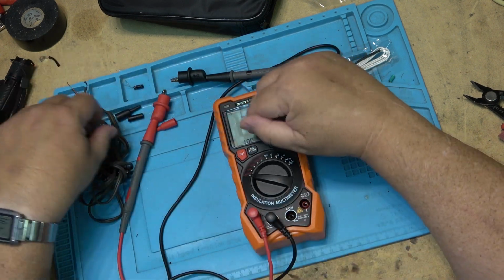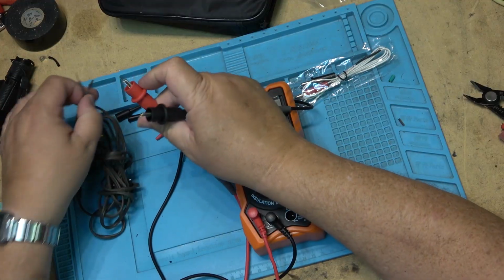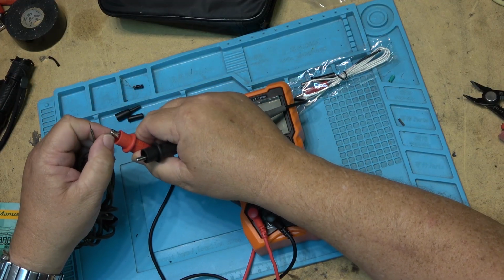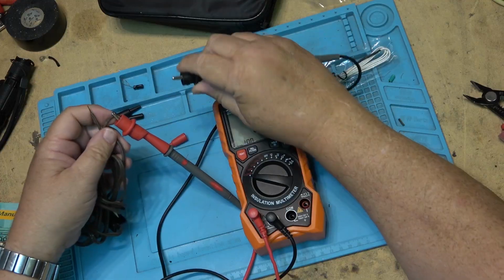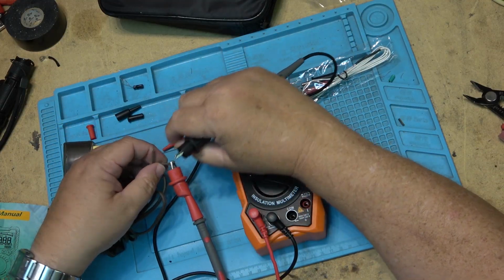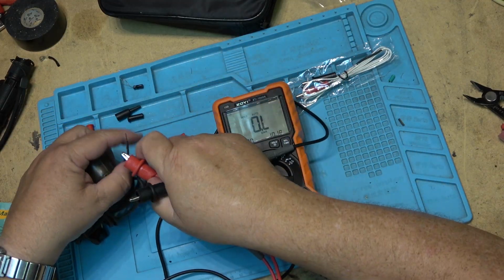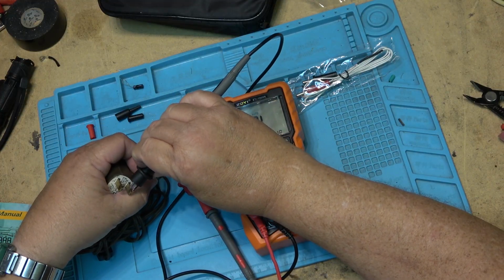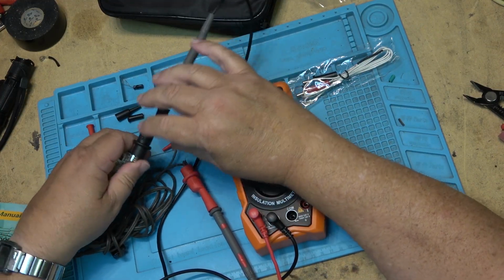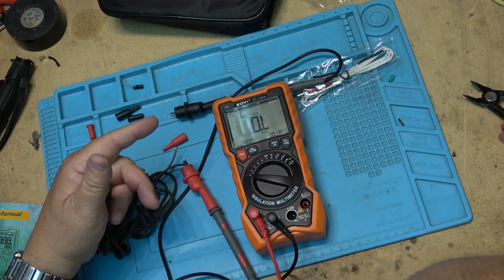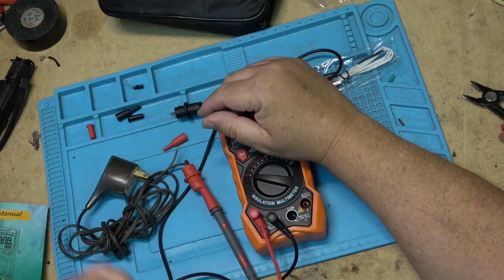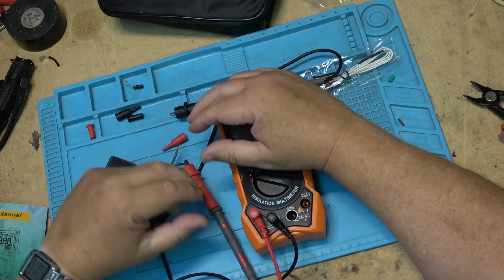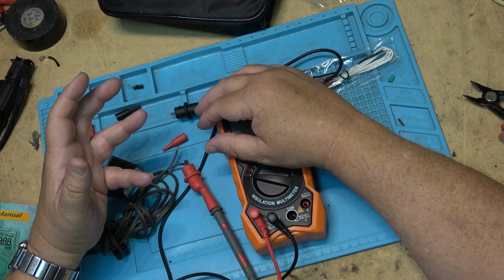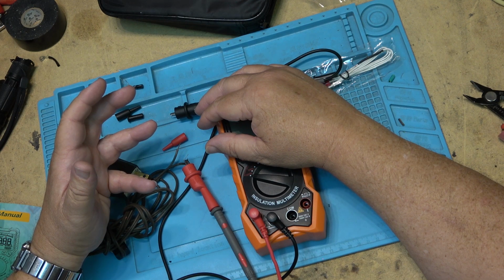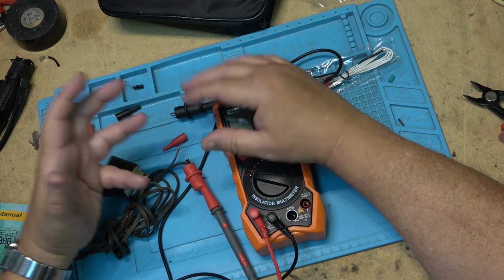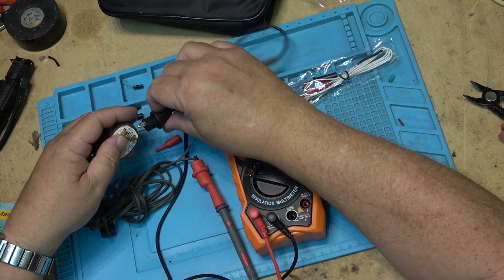So the whole concept behind a breakdown test like this is, if you've got a transformer, for example, or a motor winding or something, you don't know whether it's any good, you can connect one probe to the primary and the other to the secondary, or on your motor, connect one to one winding and the other to the second winding. I don't think I have a motor around here that I can demonstrate that on. But that's the whole idea, that you can put a high voltage across.